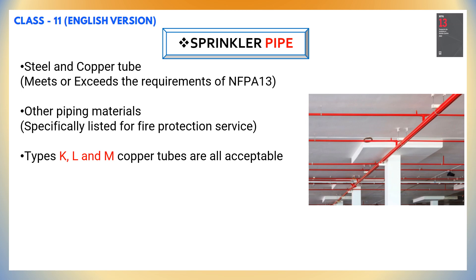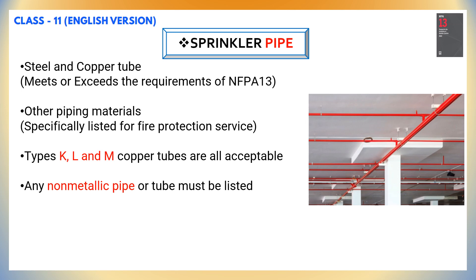Types like K, L, and M copper tubes can also be used as sprinkler piping. However, project specifications must be referred to prior to taking approval from the consultant or client. Any non-metallic pipe or tubes must be listed. As per NFPA 13, any kind of non-metallic pipes or tubes can be used, but they must be listed.